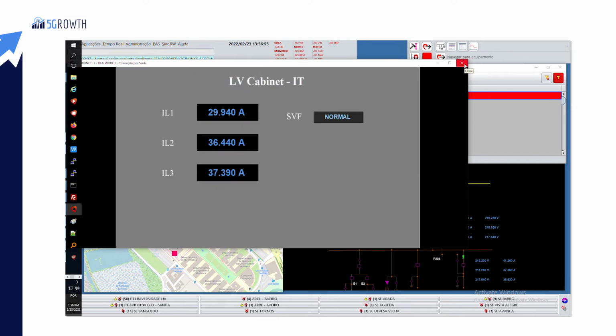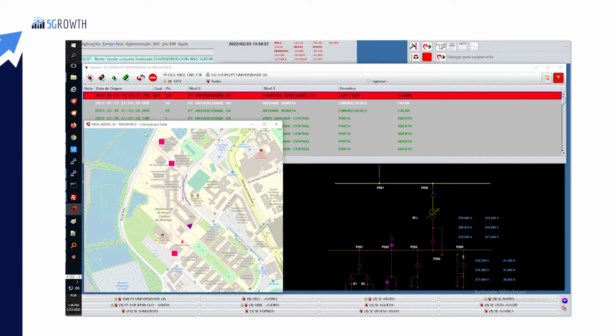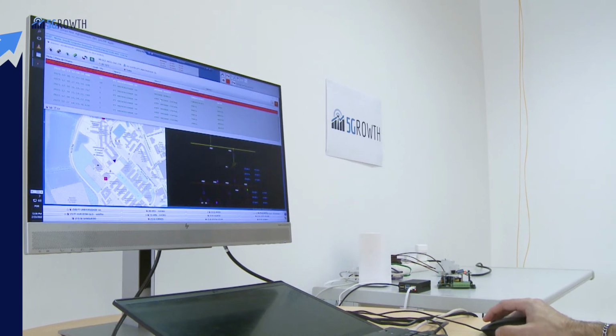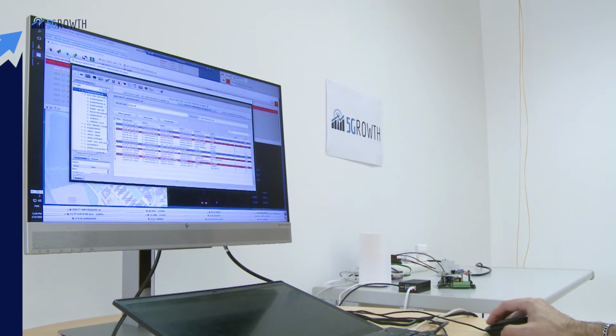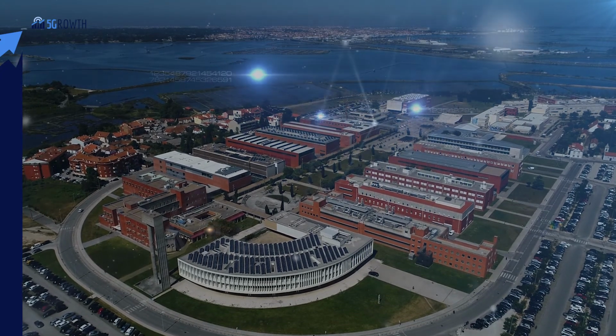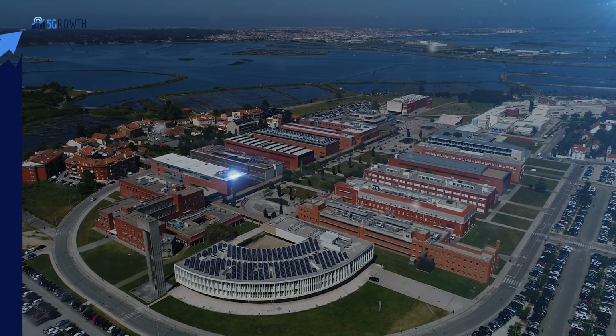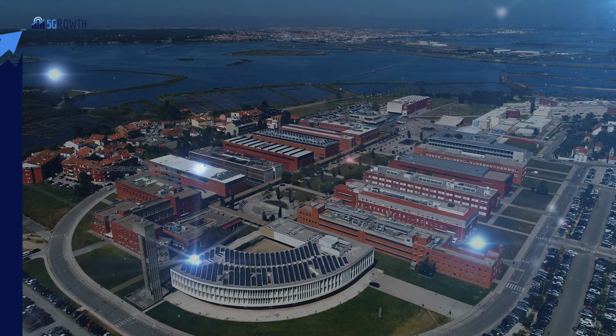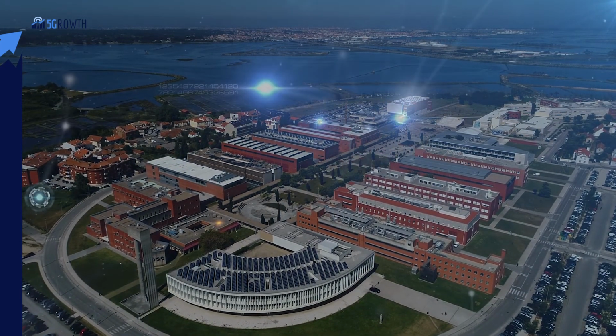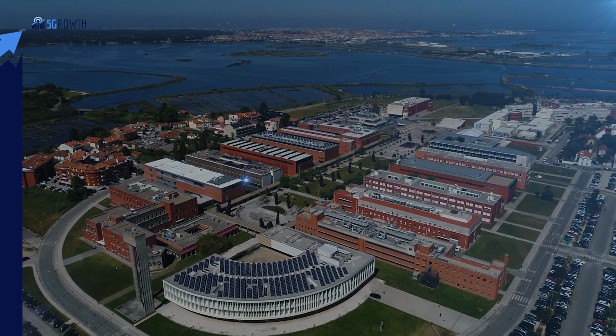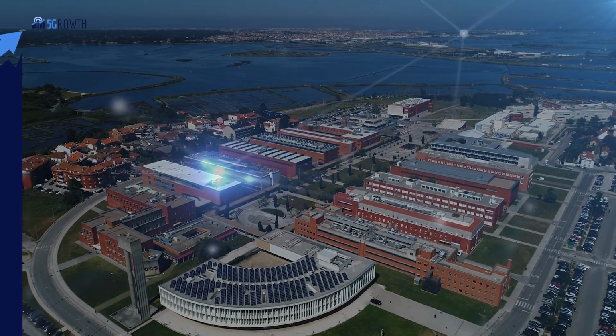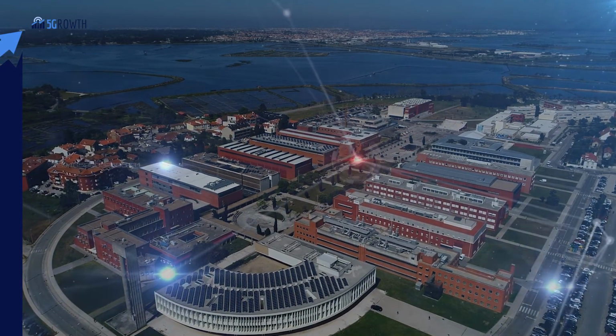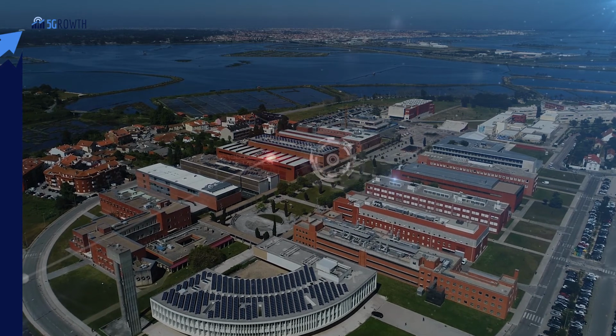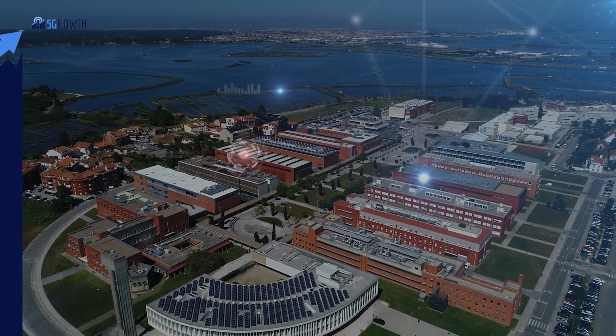A few moments after the fault occurs, the control center operator already has valuable and accurate information to pass to the field crew that will be sent to investigate and solve the problem that led to the fault. The communication technologies currently in place in many of the metering infrastructures, like PLC Prime or RF Mesh, have limitations that prevent them from supporting a large-scale real-time monitoring of the low-voltage network. The 5G provides the performance and capacity to do the job.